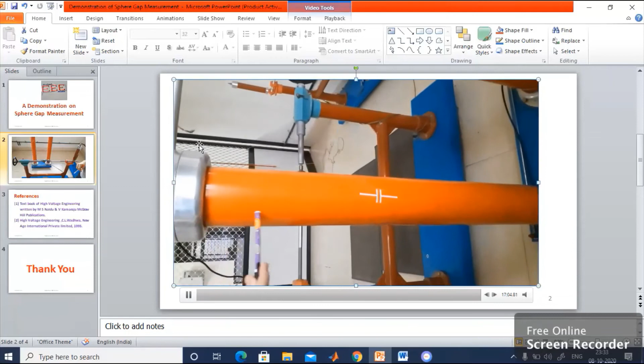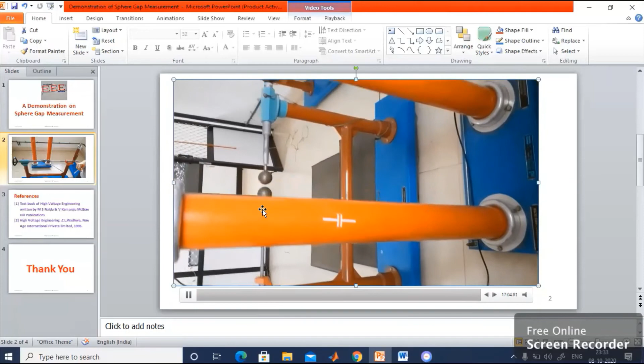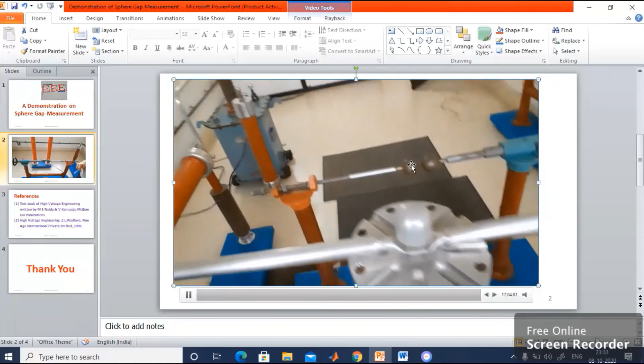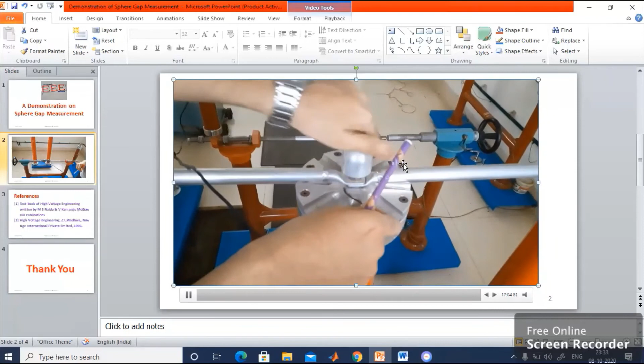Now, the output of the rectifier, either from the capacitor end or resistor end, has to be directly connected to one of the spheres. The other end will be connected to ground, so that you are capable of applying high voltage DC across the sphere gap. That's a peculiarity. You can see the connection, how I am doing that.